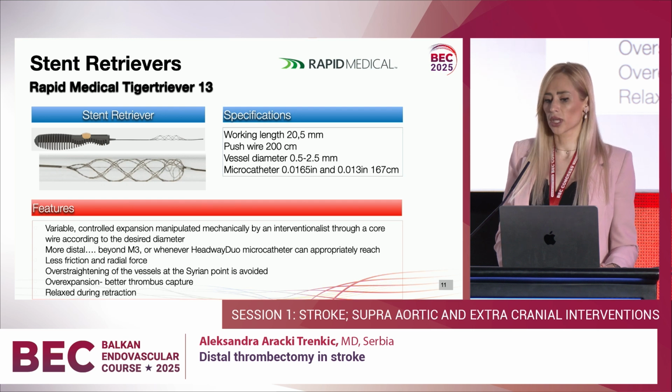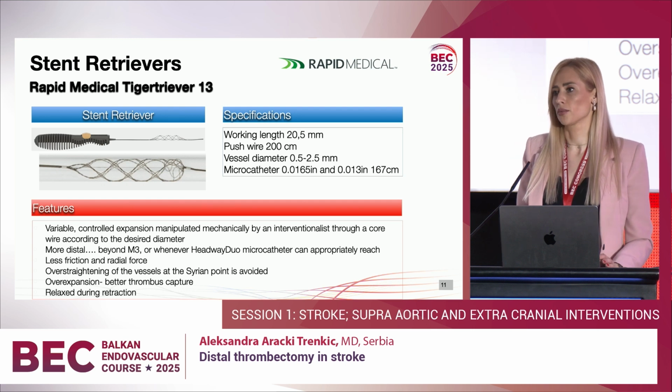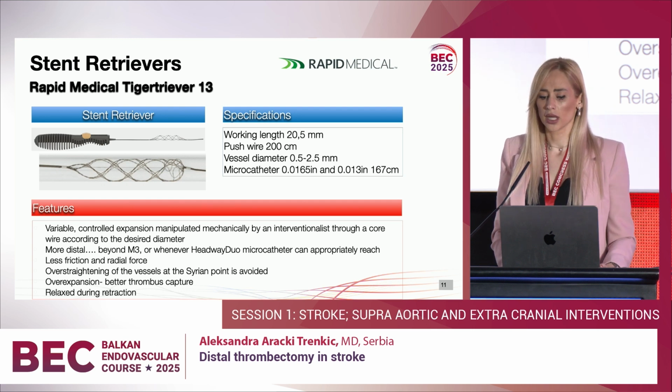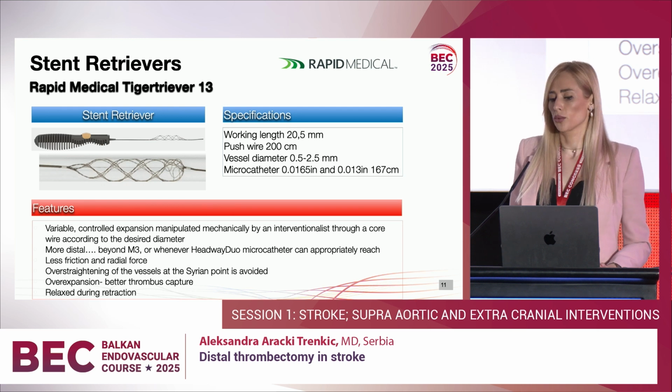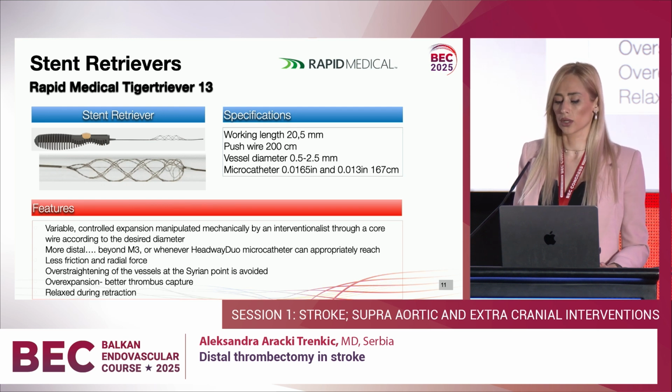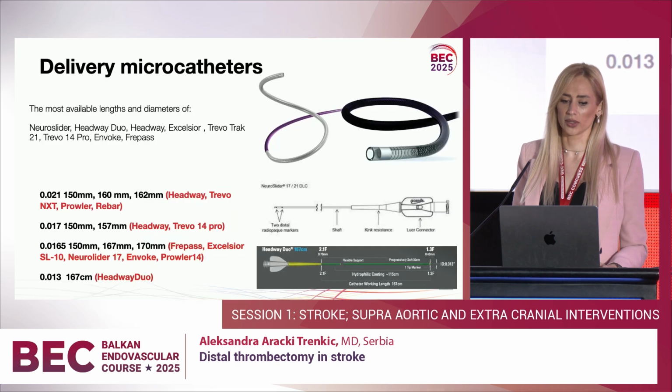Also with this stent, we can prevent the overstraightening of the artery by relaxing the stent during the extraction, and also we can better capture the thrombus due to the possibility of the overexpansion of the stent.